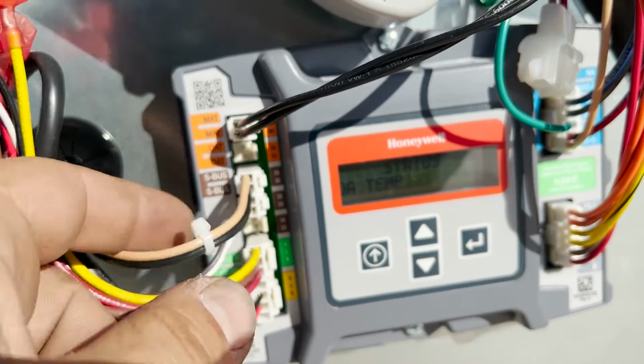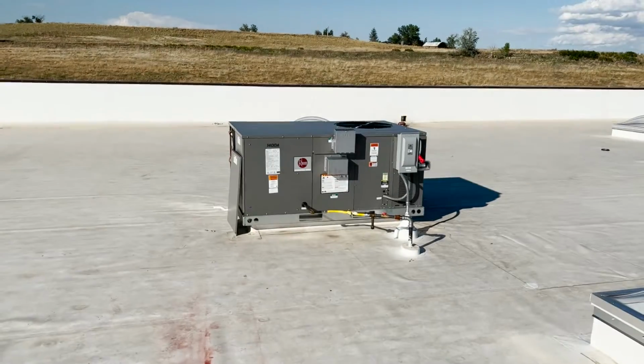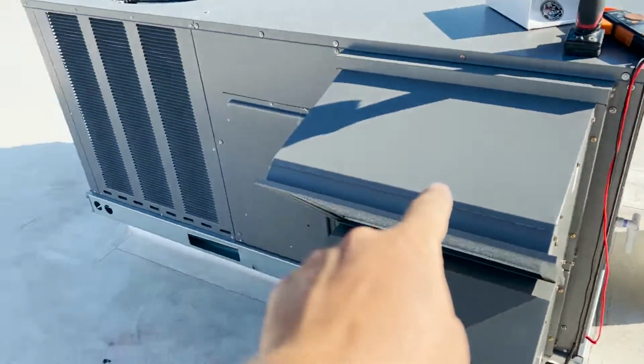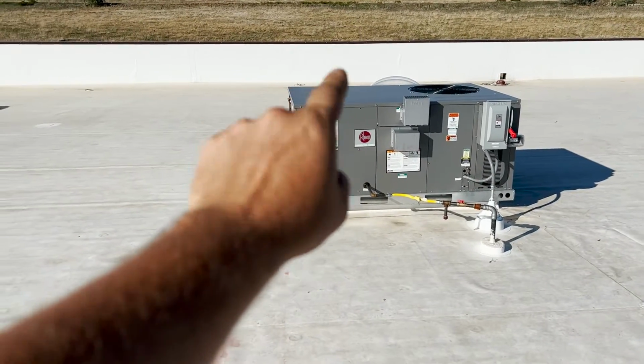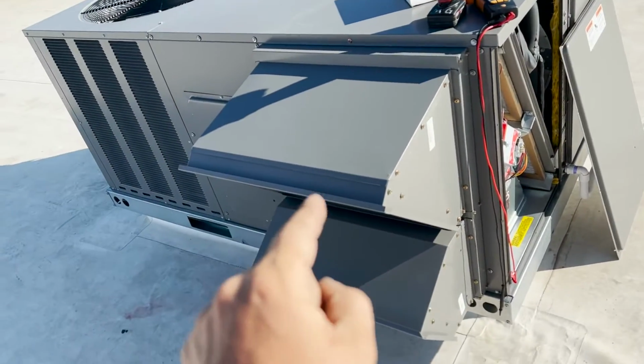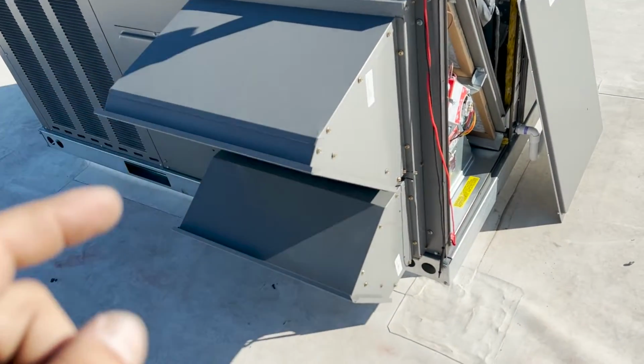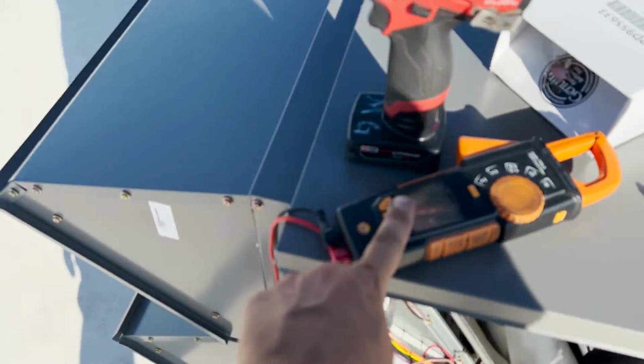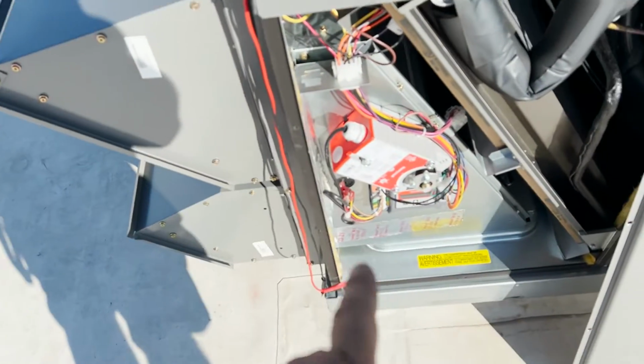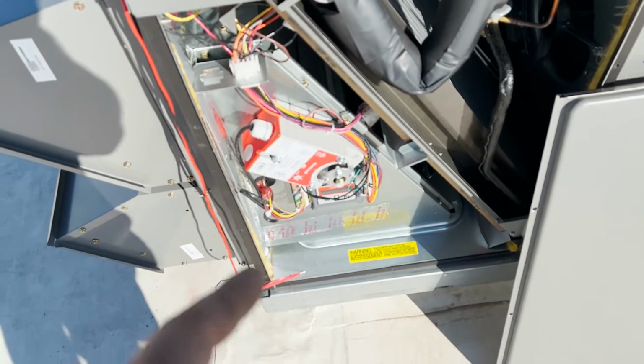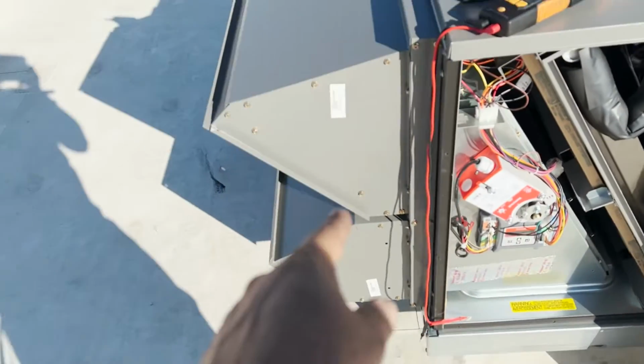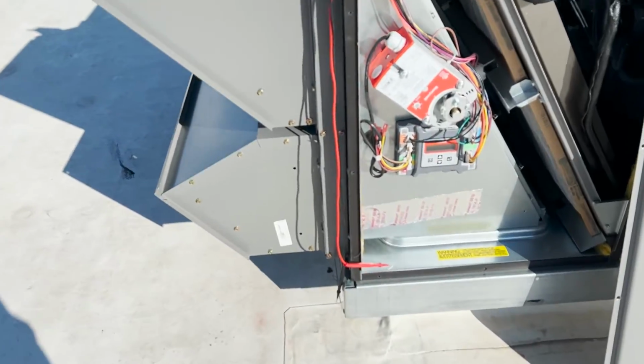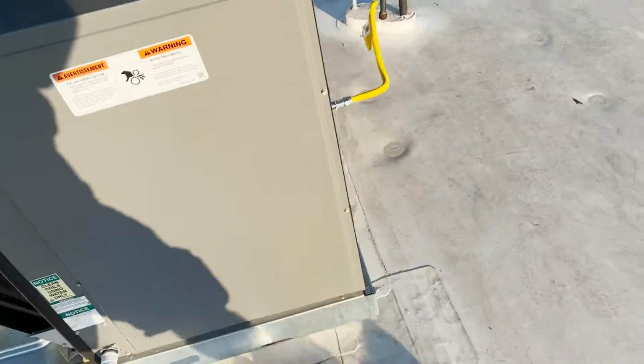So I've done a few different things. We checked the polarity. We have multiple units to go against, right? So that unit over there, we checked this sensor and it operates well in that Jade. That sensor also does not work in this Jade. I have the same kilo ohms reading on both of my sensors. This Jade is just not engaging or not being able to read a sensor in there. So I think we're gonna go ahead and switch this Jade out.